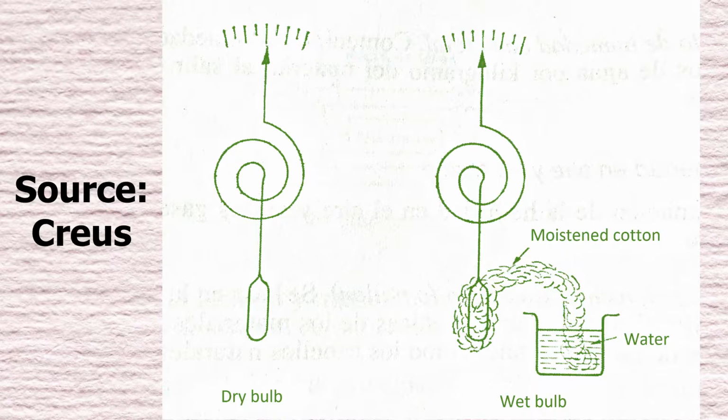This instrument is based on the capture of ambient or dry temperature and of the humid temperature by means of two thermometers, one dry and the other whose bulb is moistened. Observing in the psychrometric diagram the temperatures of the dry bulb and the wet bulb on the corresponding lines, the relative humidity is obtained by intersection.